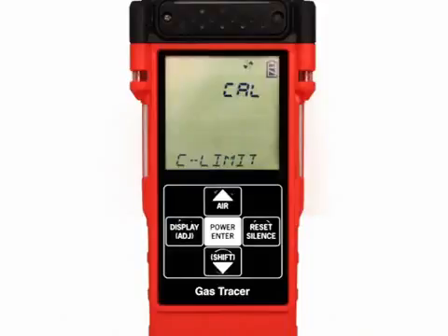If the calibration reminder item in maintenance mode is turned on, the screen that appears next depends on how the calibration expired item is set. If the unit is due for calibration and the cal expired is set for confirm to use, then the cal limit prompt will display and the alarm LEDs and buzzer will pulse several times. When this occurs, press and release the reset silence button. You will hear a beep and the startup sequence will continue.